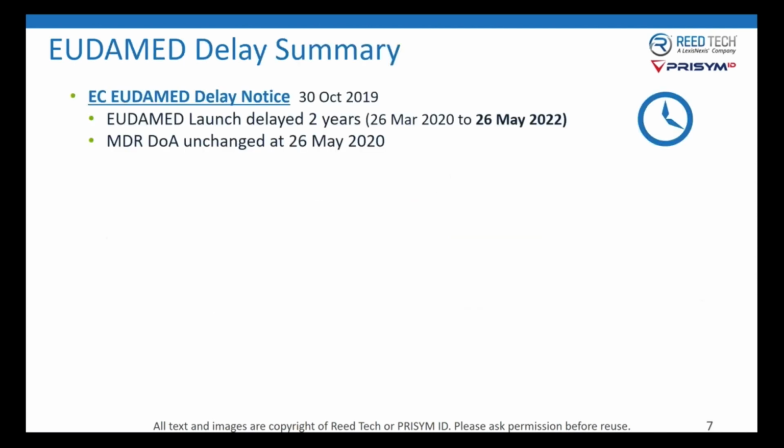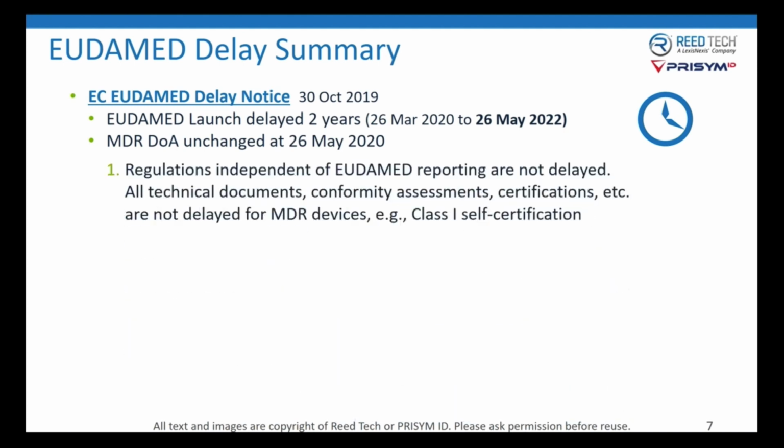The European Commission released this delay notice back in October, and as mentioned, moved the EUDAMED launch. But in the same announcement, they also mentioned that the MDR date of application would be unchanged. And that has 2 very significant impacts to you as manufacturers. Regulations that are independent of the reporting to EUDAMED are not delayed.